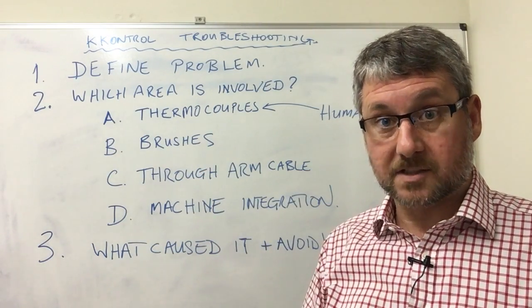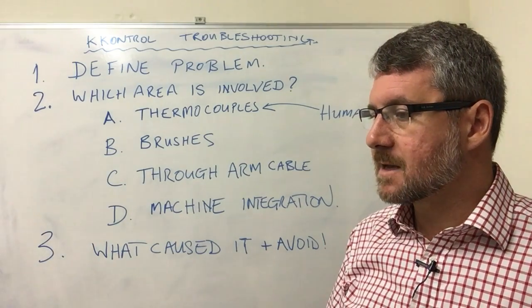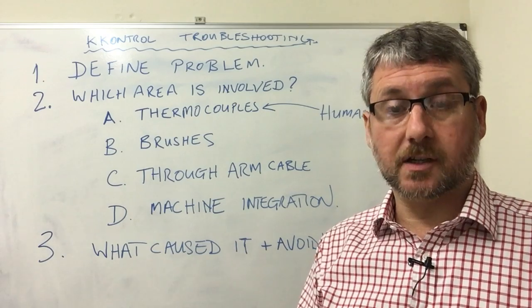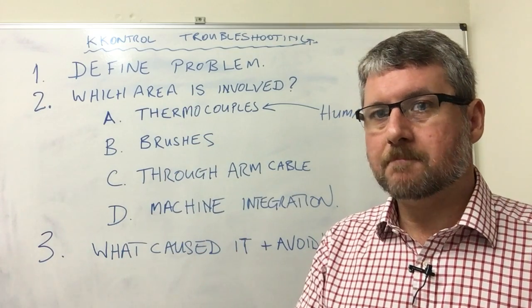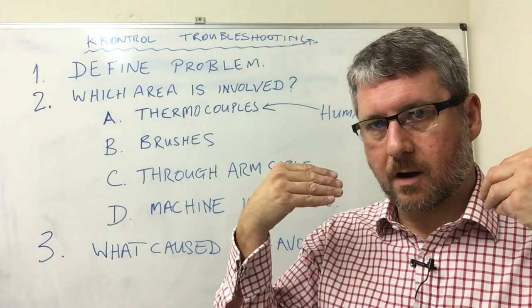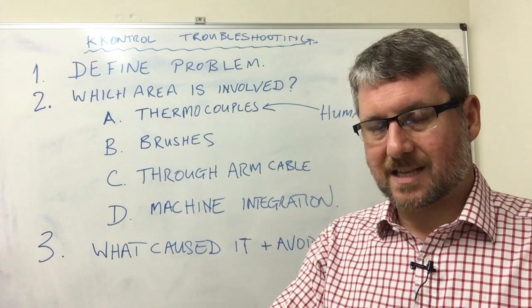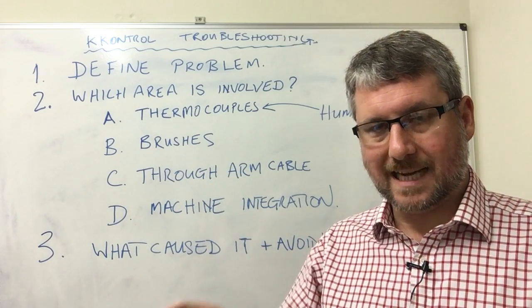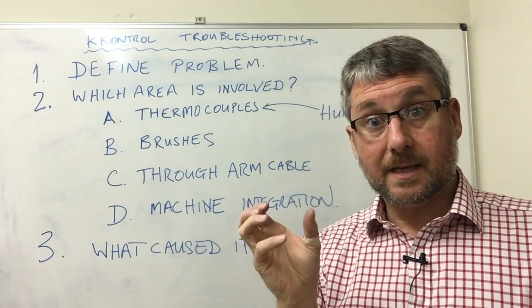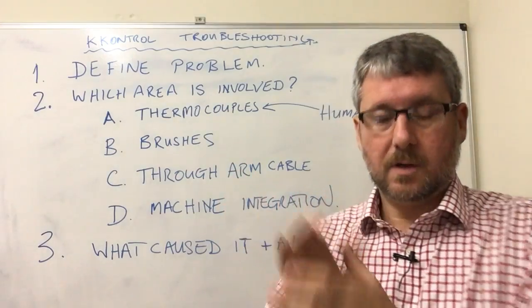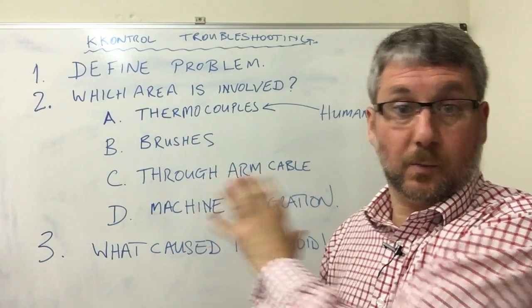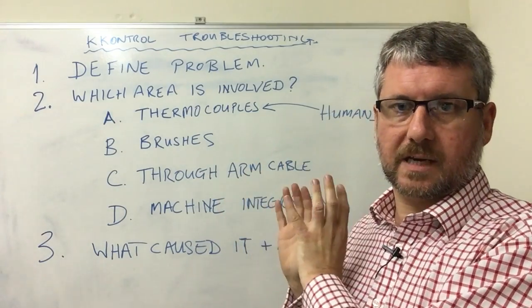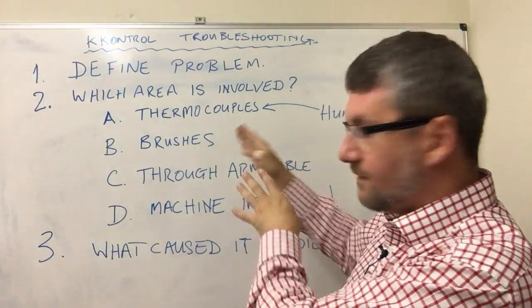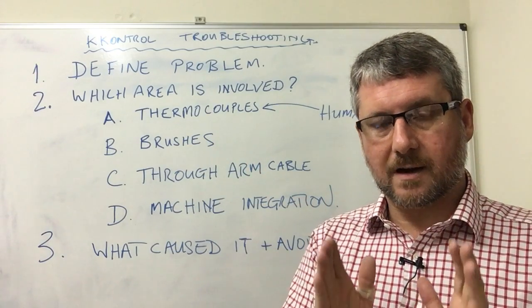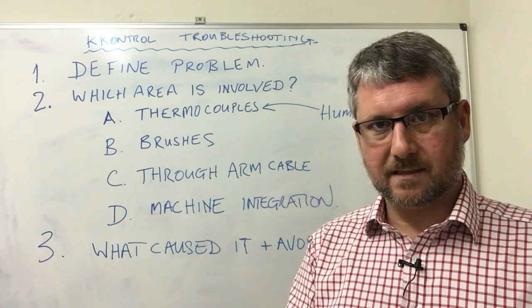So if we drop a channel altogether, it could go open circuit. Often it goes open circuit, no thermocouple attached because a brush is disengaged from the system. Change the brushes. If you are maintaining the slip ring itself regularly, making sure nuts and bolts are tightened, plates are parallel, the brushes have not been worn away too low, then you don't really have a problem. We have not found problems with brushes. Okay, this is 10 years developed. Okay, so issues are if the system is not maintained.